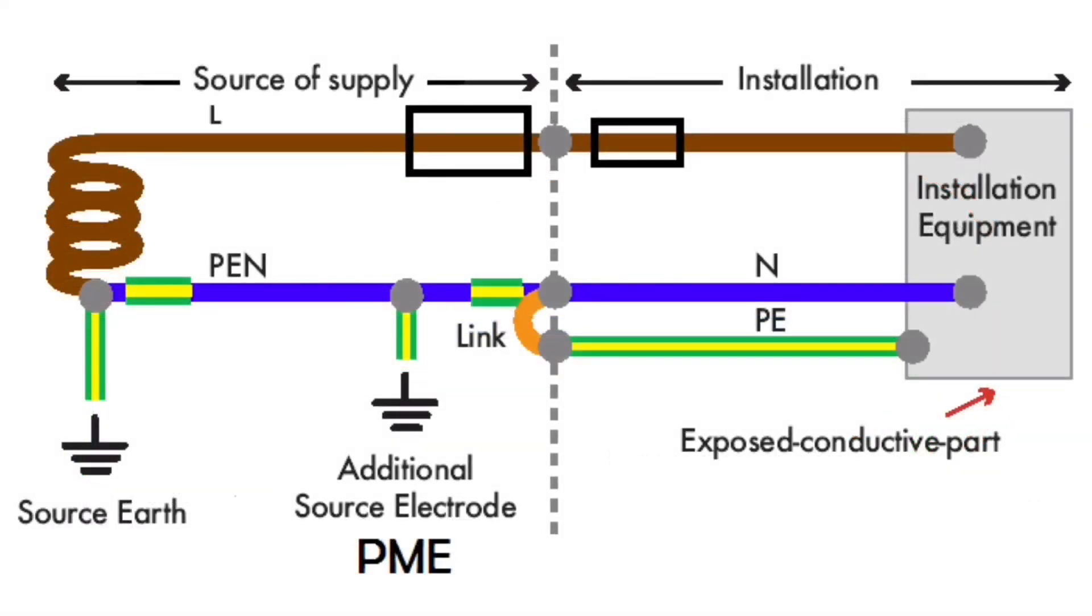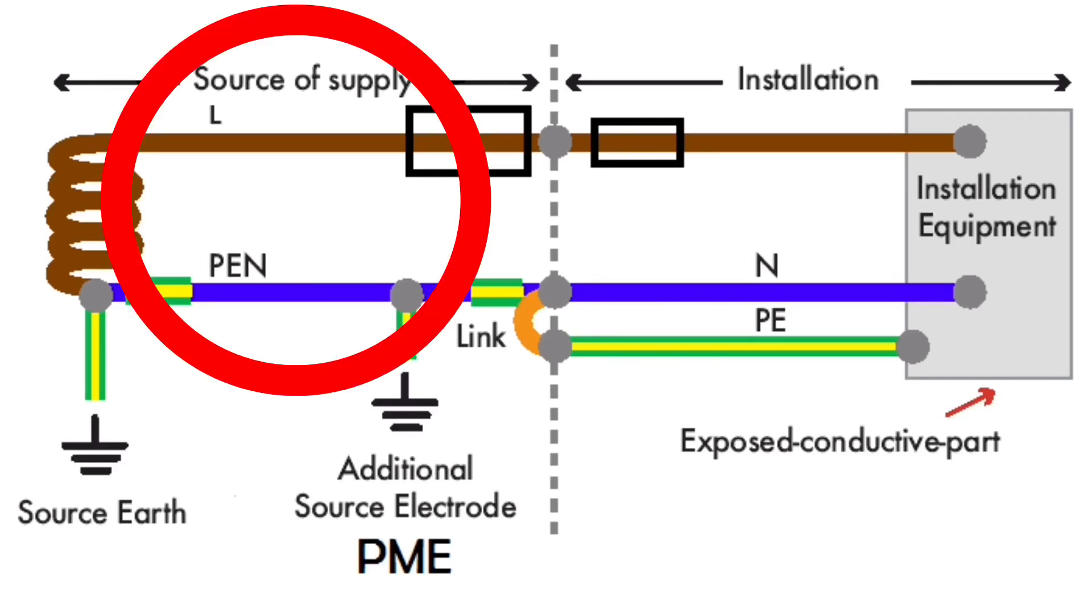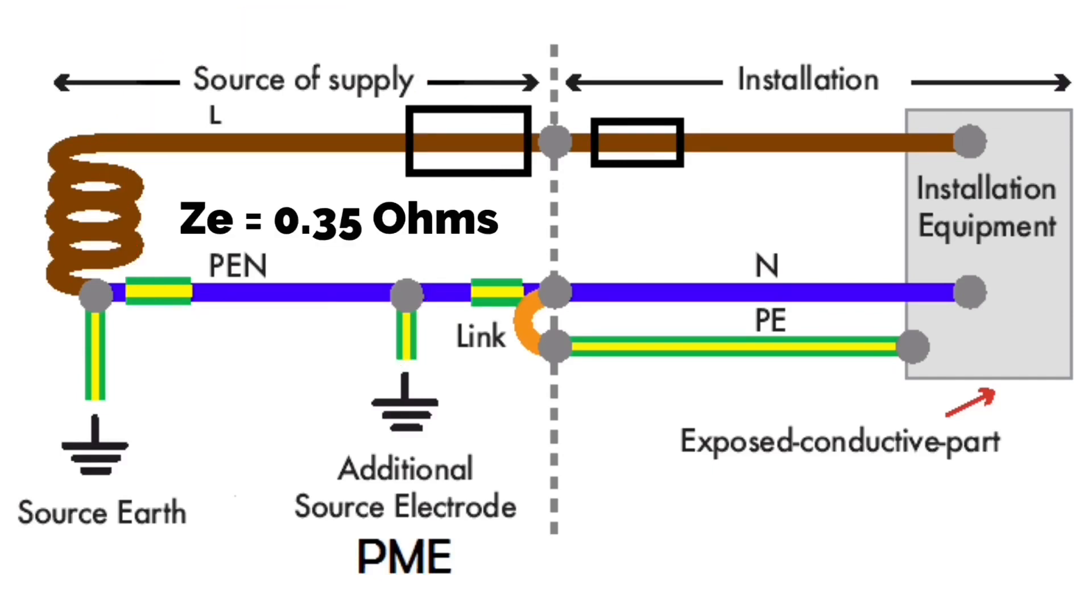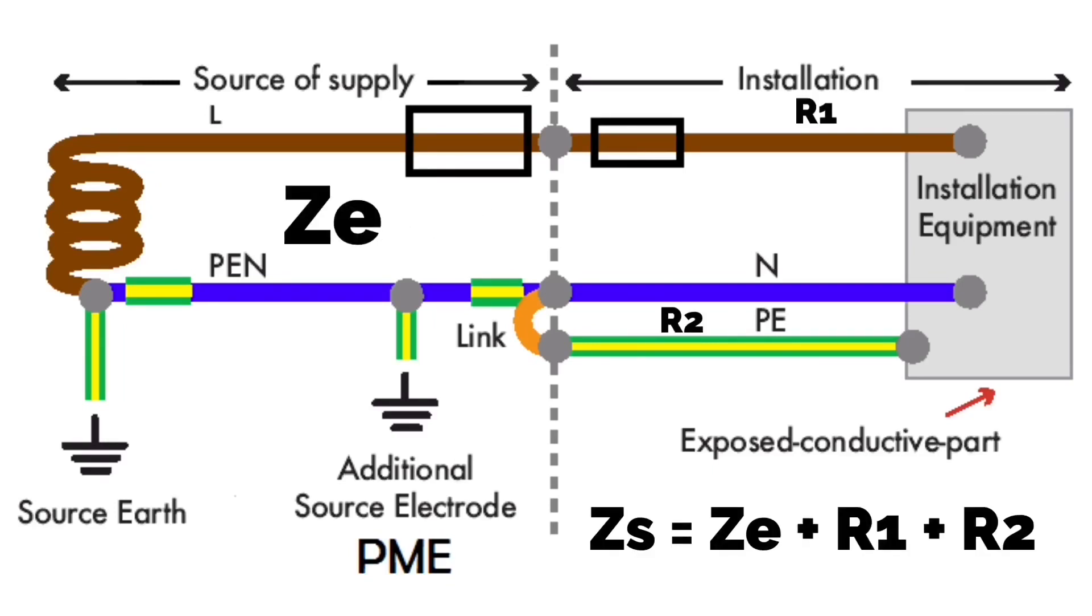This drawing shows a TNCS earthing arrangement, and the supply authority's cable now has a maximum external impedance ZE of 0.35 of an ohm. Total circuit impedance ZS is still ZS equals ZE plus R1 plus R2.